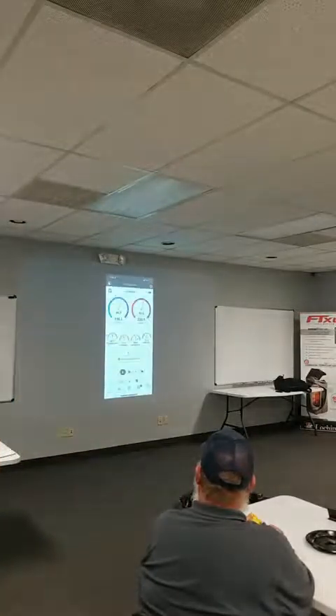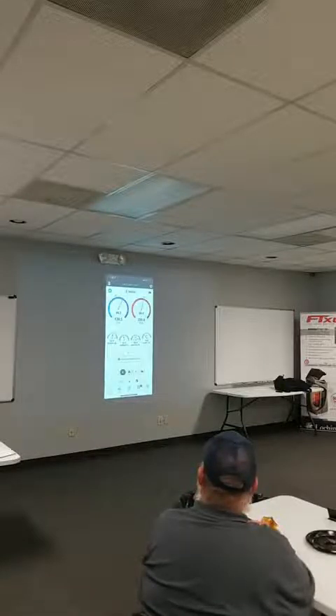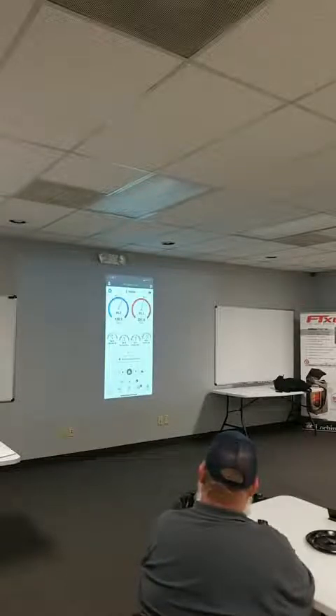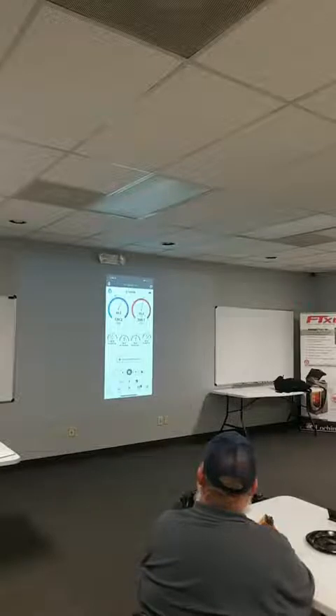All right, and we got really, really high suction pressure on this. I think we're pulling in return air that's not representative. Let's see, our outdoor air is 74, our return air is 68, so we're definitely short cycling air in there. It's seeing 68 degree return air, but it's actually pulling in mixed air. This is stratified air again. If we move the probe to the other side, it'll probably go right into range. It's just seeing that cold air temperature, and that's why it's giving us an issue.